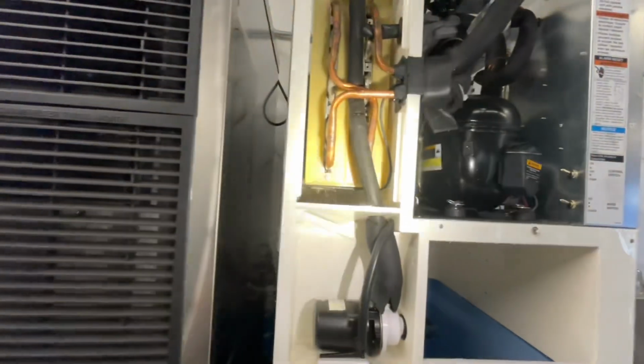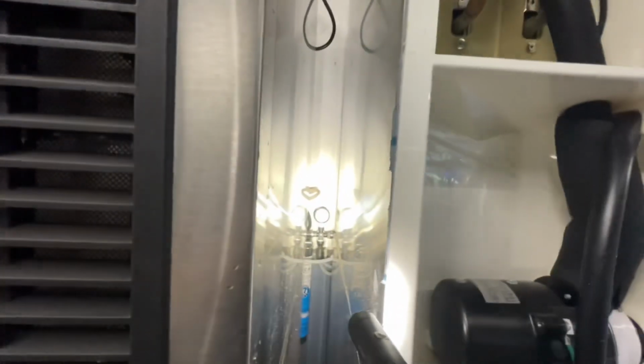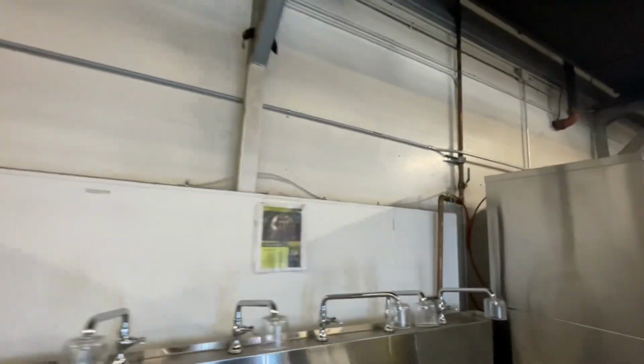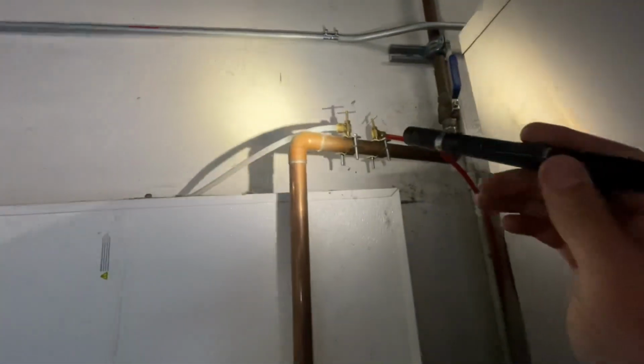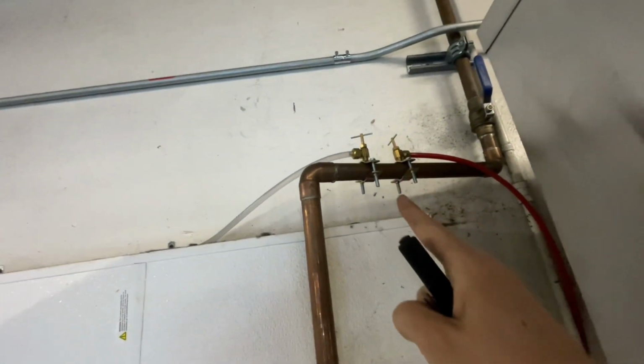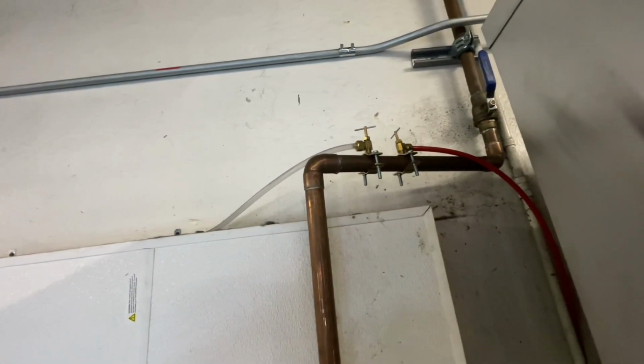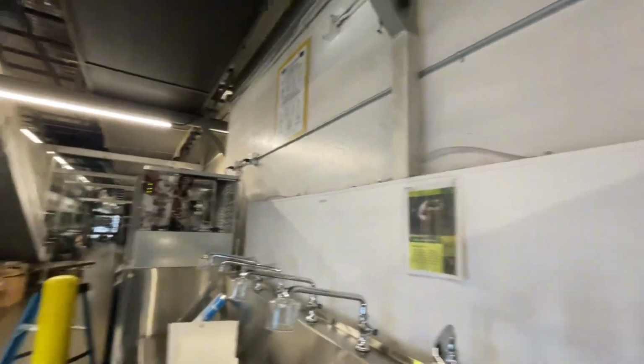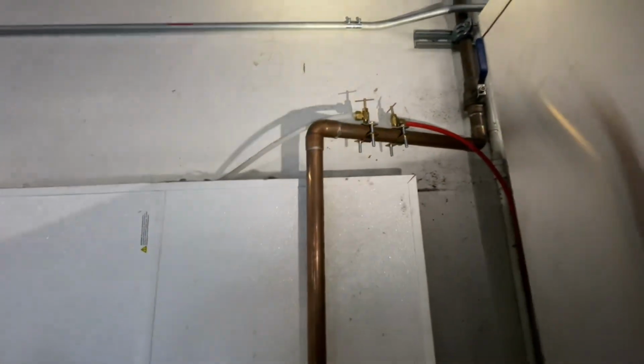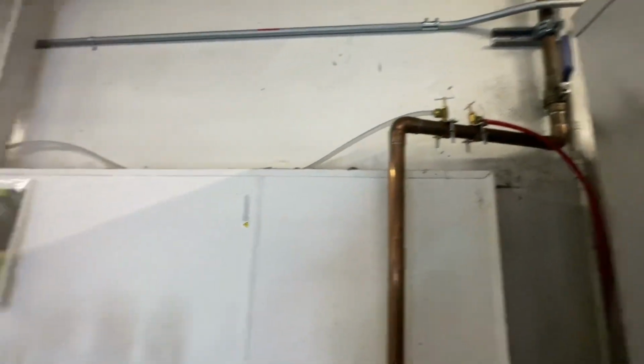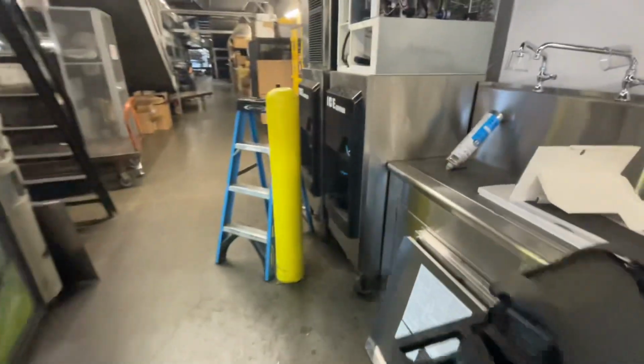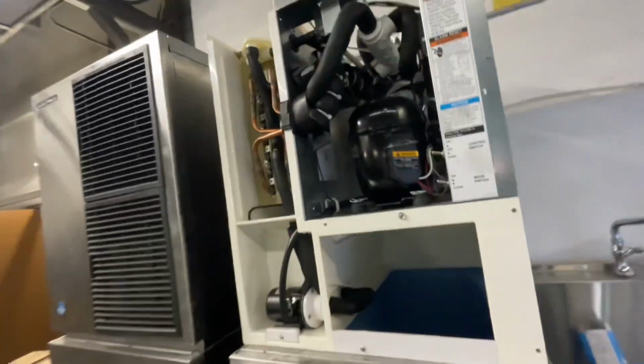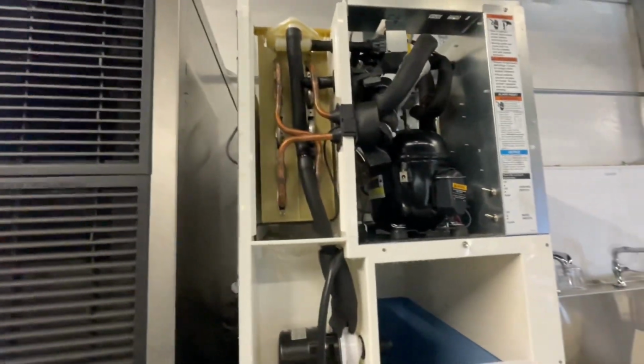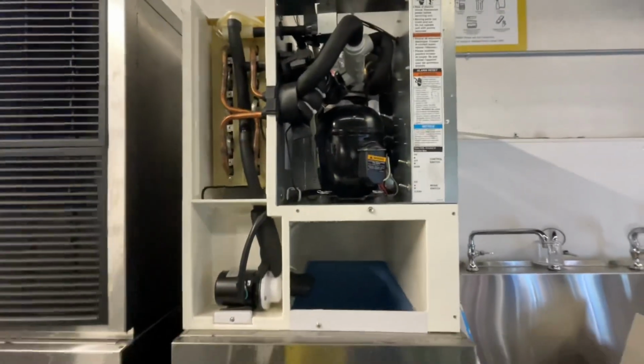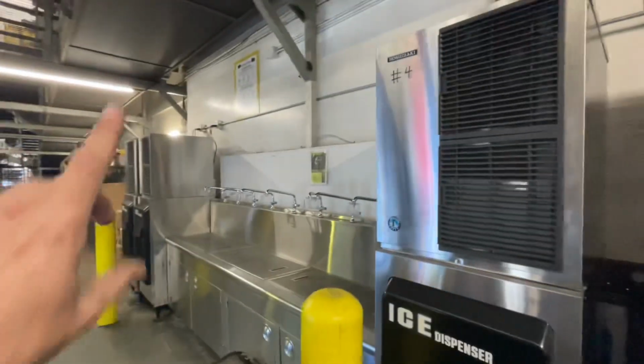So, although my water flow improved a little bit, my water gauge back there is still teeing out at 0. I traced the source of the problem back to this guy right here, not letting enough water flow through. That's not the right way to do it, especially for these water hog Hoshizakis. I'm going to recommend they change that setup, although the response I'll get is, well, it's been working for years, we don't need to change it. And I'll say okay, and then they'll call me back, and we'll have this conversation all over again. All done with that one down here.